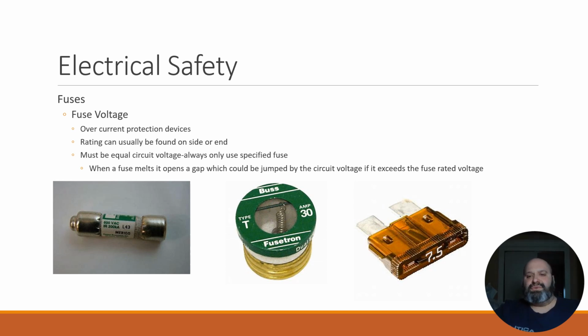So with fuses, you always want to use the proper rated fuse. You don't want to use a larger fuse. One thing that I was taught wrongly when I was new is that you can always go up in rating, just don't go down. And functionally, that will fulfill the purpose. Here's the problem: if you go too high, then if there is overcurrent, you're not protecting the circuit, and you could actually damage a component within the circuit.